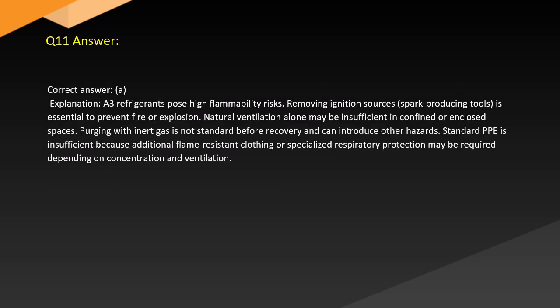Answer. Correct answer: A. Explanation. A3 refrigerants pose high flammability risks. Removing ignition sources, such as spark-producing tools, is essential to prevent fire or explosion. Natural ventilation alone may be insufficient in confined or enclosed spaces. Purging with inert gas is not standard before recovery and can introduce other hazards. Standard PPE is insufficient because additional flame-resistant clothing or specialized respiratory protection may be required depending on concentration and ventilation.